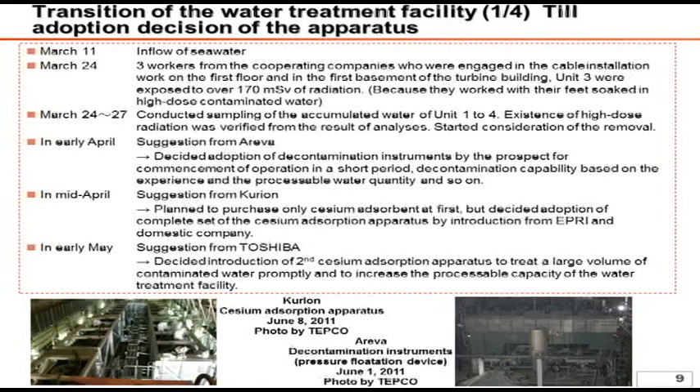Here I would like to go over the track record of the installation of the water treatment system. After the earthquake on March 11th, a large amount of seawater flooded the turbine buildings and reactor buildings. Afterwards, on March 24th, three workers laying cables inside the contaminated water in the basement and first floor of the Unit 3 turbine building were exposed to more than 170 millisieverts. This incident revealed that there was extremely highly contaminated water inside the facilities, which urged the necessity for countermeasure planning. In early April, Areva proposed the use of decontamination instruments and Kurion's proposal was received in the middle of April. In early May, Toshiba also made a proposal. These proposals serve to maintain the diversity of the systems, and we have decided to install Kurion and Toshiba's cesium adsorption apparatus and Areva's decontamination instruments.